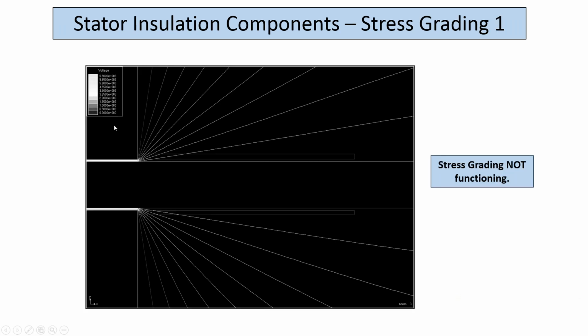So this slide shows, the left-hand side is the end of a core. The center is a stator conductor. It's represented as one conductor, and then the lines that emanate from that central point are your electric field lines. So the one closest to the core is 0 kV, and then they jump up at approximately 1 kV per line. And you can see that the lighter shade, the cylindrical.